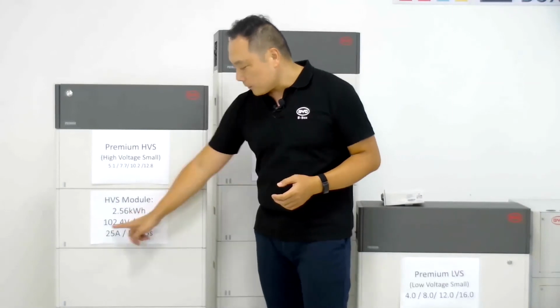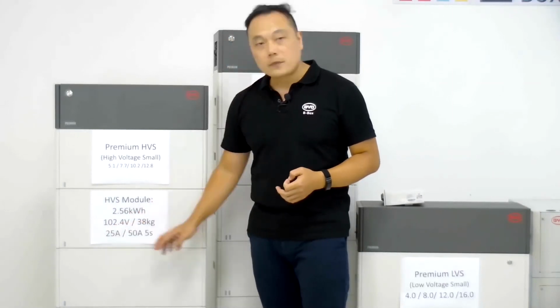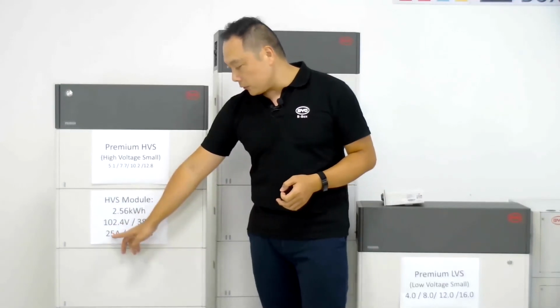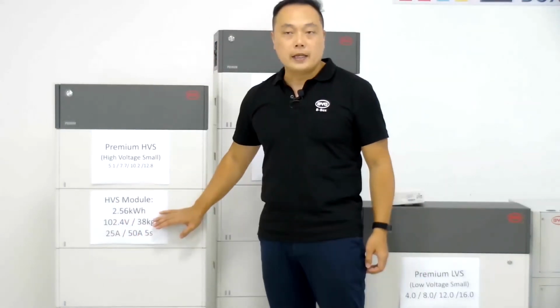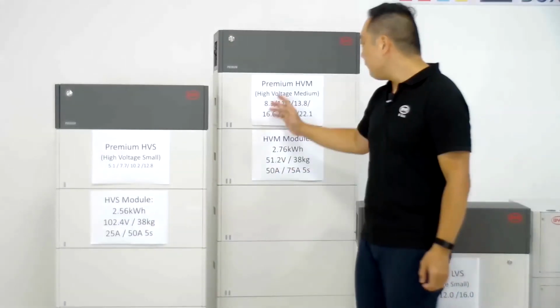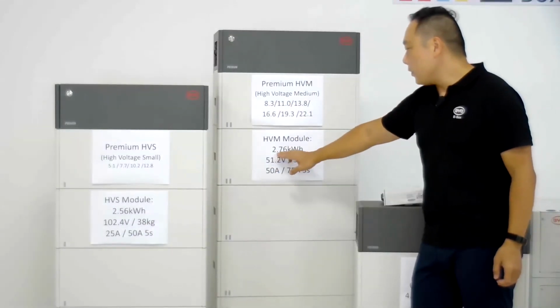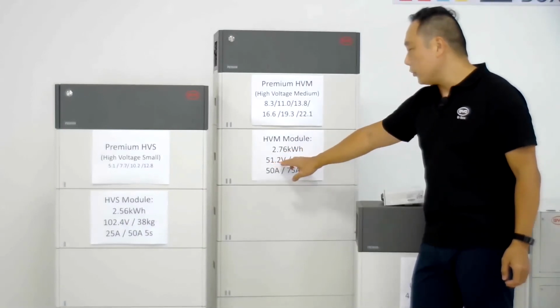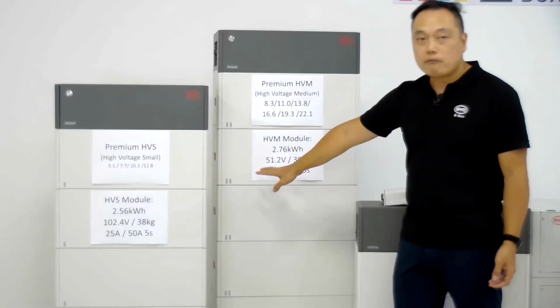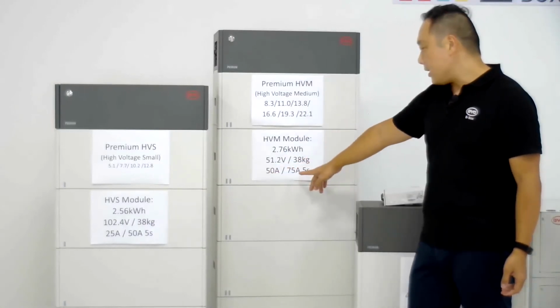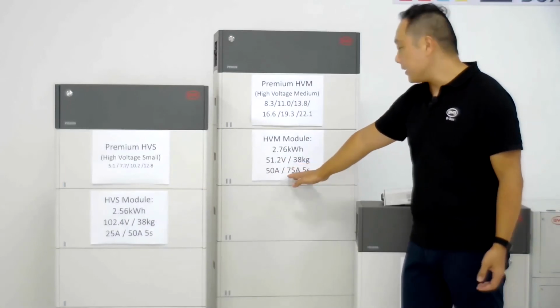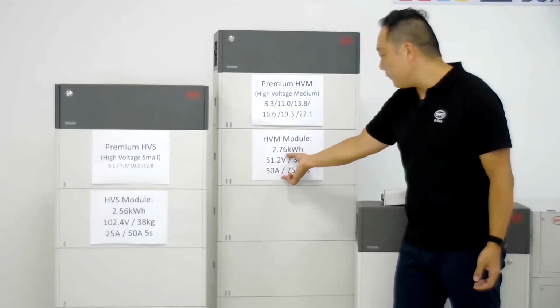2.56 kilowatt hours, 102 volts, 38 kilos. It can output 25 amps continuously and 50 amps for 5 seconds, right? If you multiply voltage and current, you get 2.5 kilowatts, right? And have a look at HVM. Each module is 2.76 kilowatt hours. It's 51.2 volts, which means that's the normal 48 volt, as we call it. 38 kilos. Continuously, it can output 50 amps. And the surge or peak current is 75 amps for 5 seconds. If you multiply current and voltage, that's also 2.5 kilowatts.